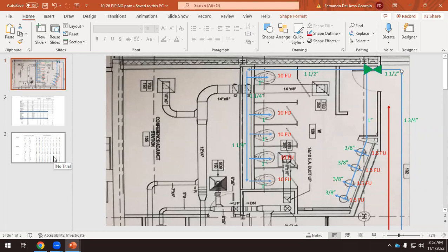Okay, so now things change because what's the number, the total number of fixture units? Okay, so now I have a vertical pipe and I have restroom 1 with 56 fixture units. The second, the third, and the 4th. Okay, so I have 4 restrooms, and I think we did the gentleman restrooms last week, but I don't remember.